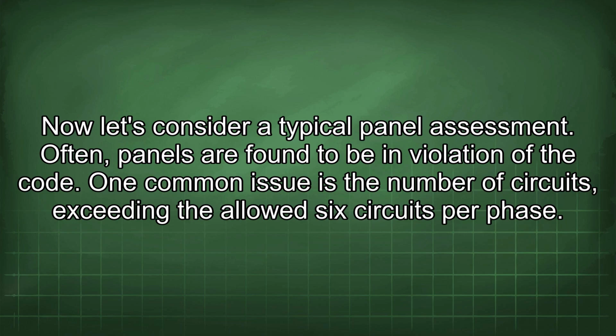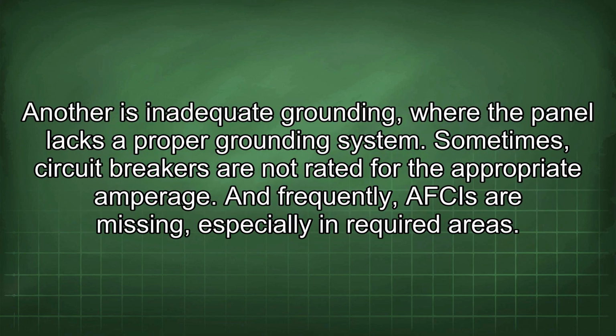Now let's consider a typical panel assessment. Often, panels are found to be in violation of the code. One common issue is the number of circuits exceeding the allowed 6 circuits per phase. Another is inadequate grounding, where the panel lacks a proper grounding system. Sometimes circuit breakers are not rated for the appropriate amperage, and frequently AFCIs are missing, especially in required areas.